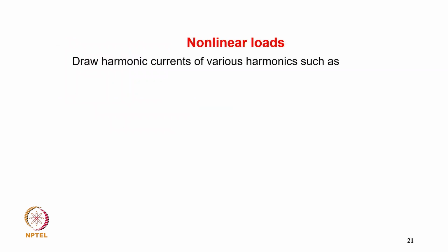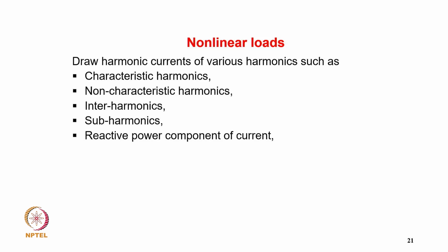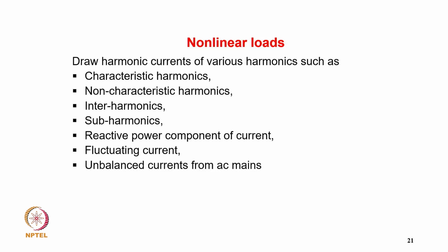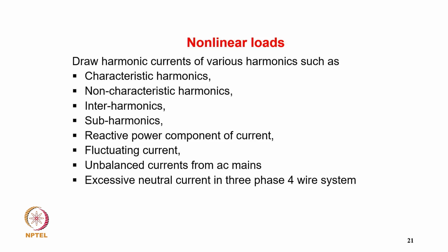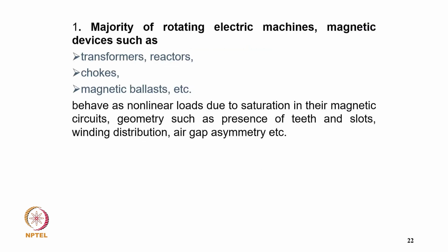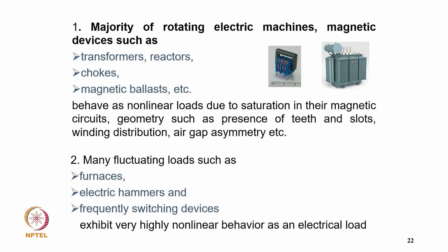So a nonlinear load draws harmonic currents of various kinds such as characteristic harmonics, non-characteristic harmonics, interharmonics, subharmonics, reactive power component of current, fluctuating current, unbalanced current from the AC mains, and excessive neutral current in a three-phase four-wire system. The majority of rotating electrical machines and magnetic devices such as transformers, reactors, chokes, and magnetic ballast behave as nonlinear loads due to saturation in their magnetic circuit geometry, such as the presence of teeth and slot winding distribution, air gap, asymmetry, and many fluctuating loads. Furnaces, electric hammers, and frequent switching devices exhibit very highly nonlinear behavior as an electrical load, like an electric hammer.